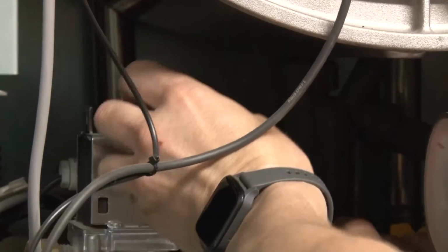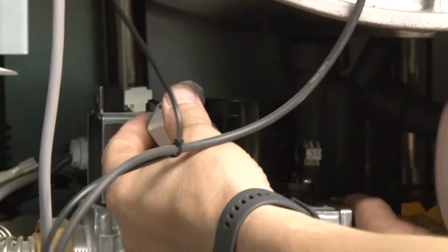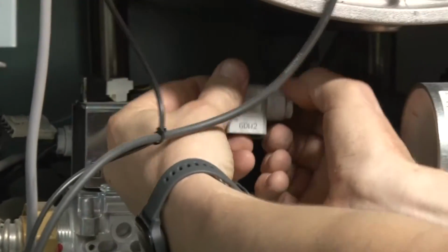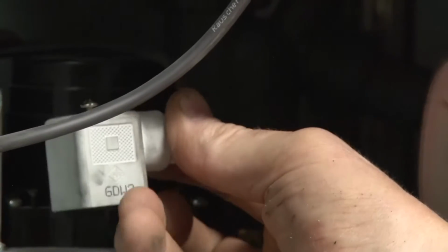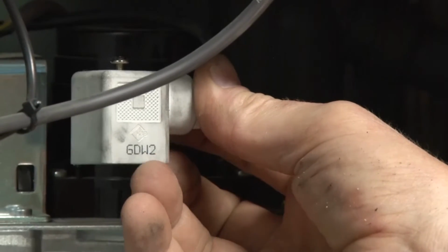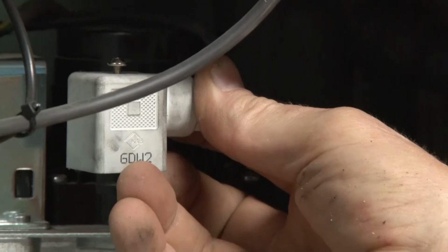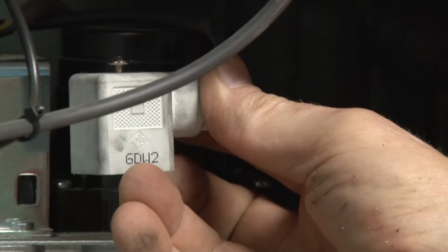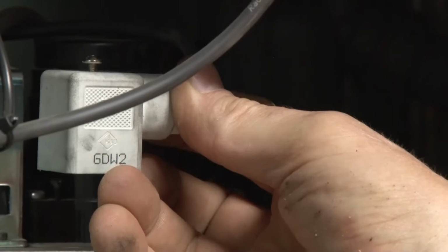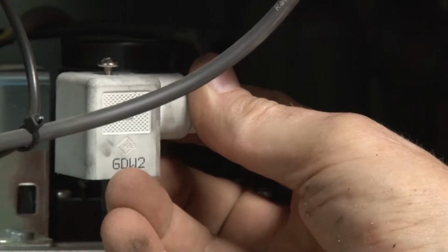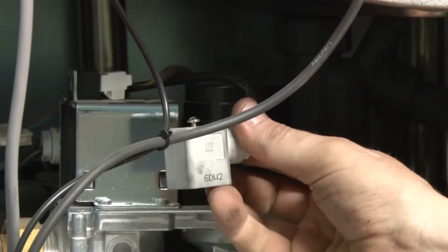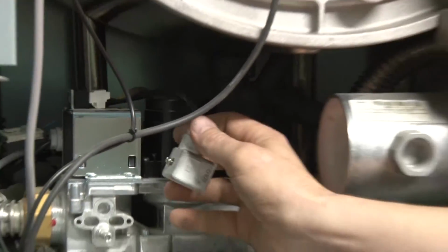There's a little gas pressure switch in there. And the gas pressure switch I have to remove the coil from. You'll see there is GDW2. I'm going to butcher some German here. That's Gas Drucker Wasser 2, gas pressure switch. And basically, there's another gas pressure switch on the backside of this gas valve, which is GDW1. That's a low gas pressure switch.